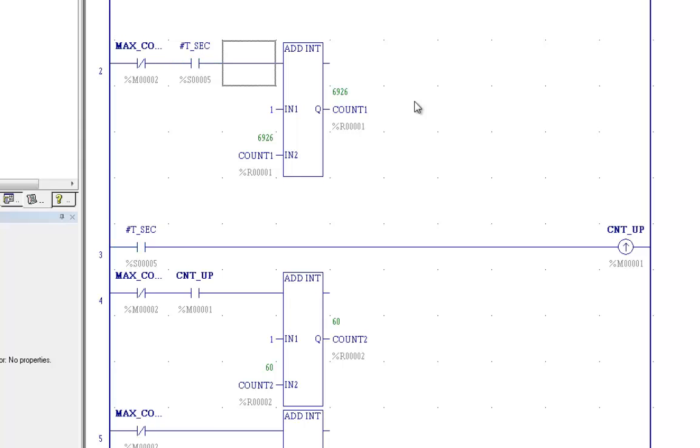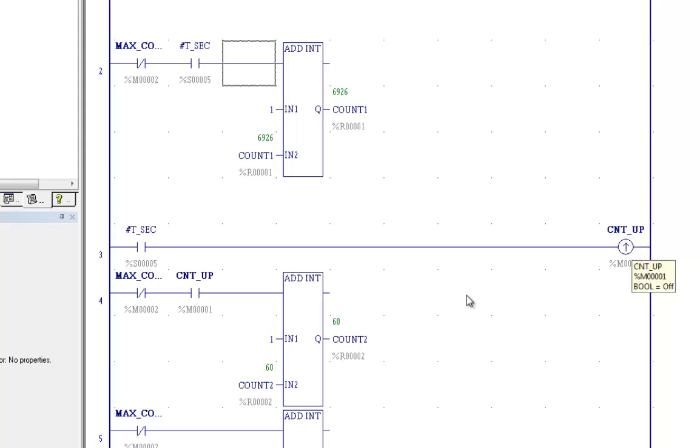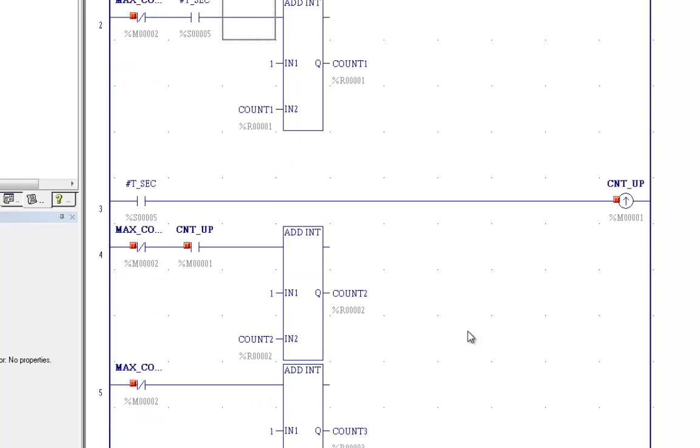So if you look at this, when you do an add function, you only want to add one for every occurrence of something happening. You need to use a positive transition coil. And that would account for any of these functions over here. You only want to have the operation take place once. In the next we'll talk about adding and subtracting. And we'll go on from there.